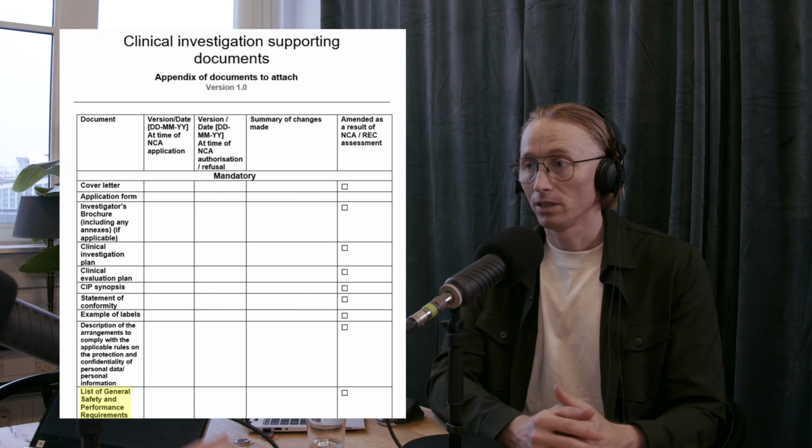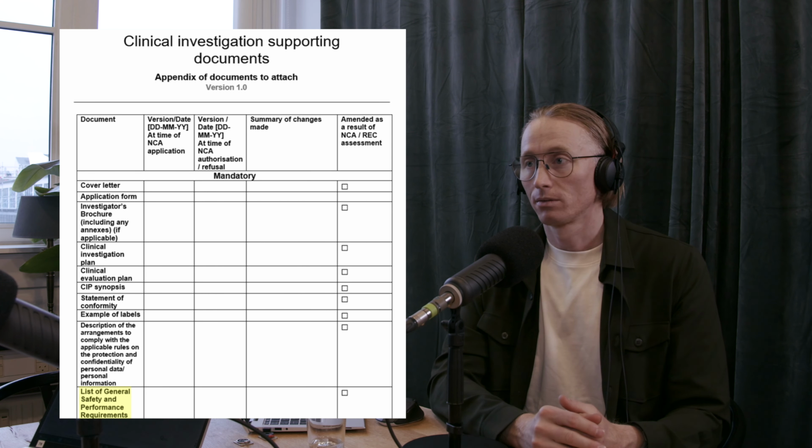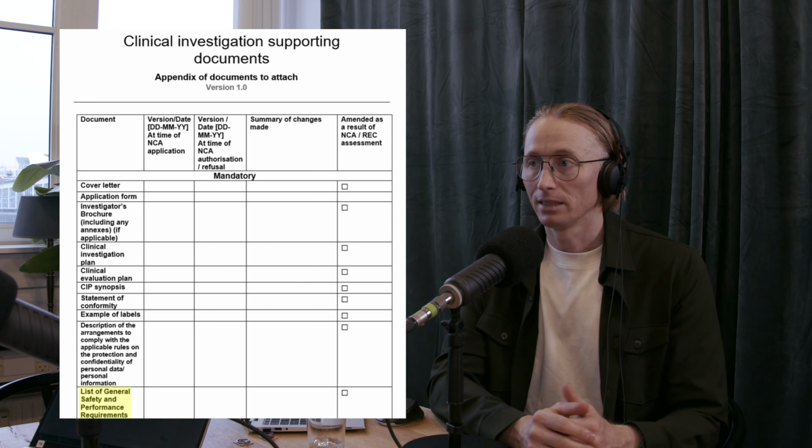So early on, you wouldn't know the document number for a certain document that is actually the reason why you fulfill a certain requirement. And for most of our clients and for most devices, they need clinical studies, and this is one of the documents that you need for submission. So starting early and evaluating what documents you actually need to prove is also a good thing.